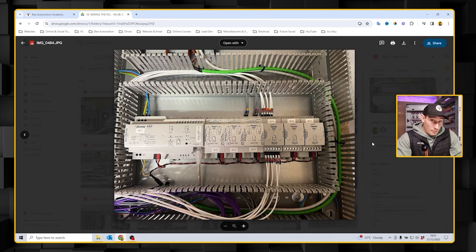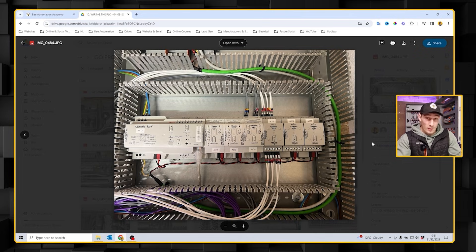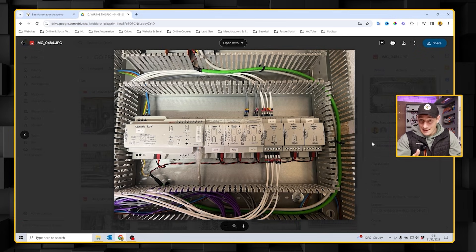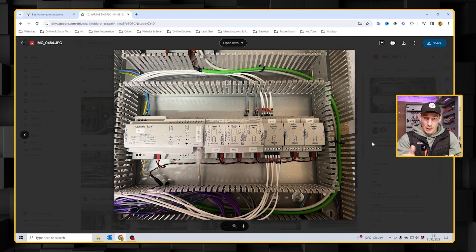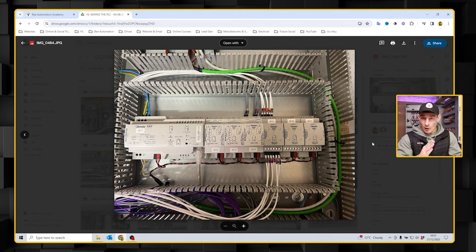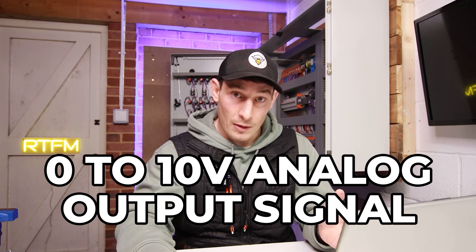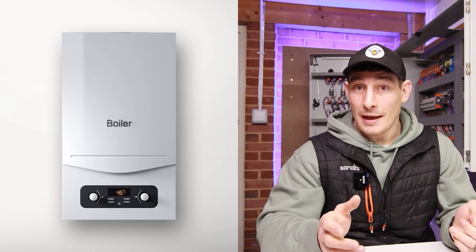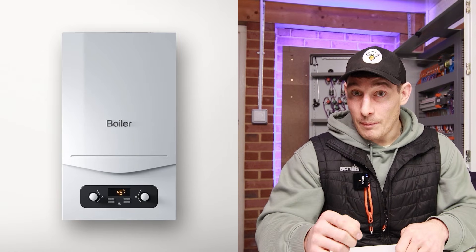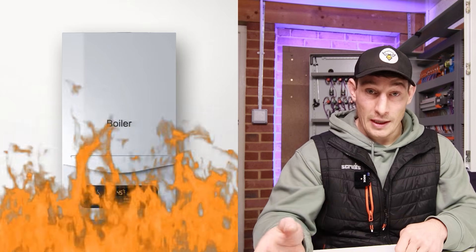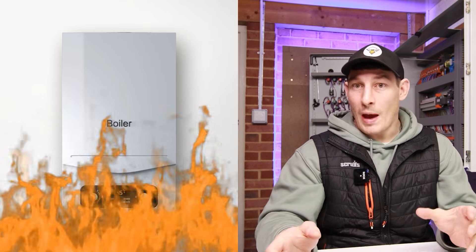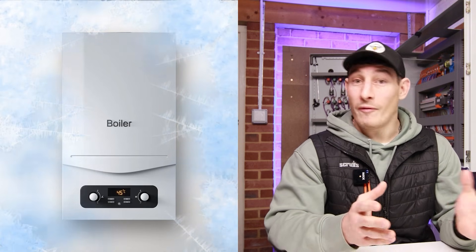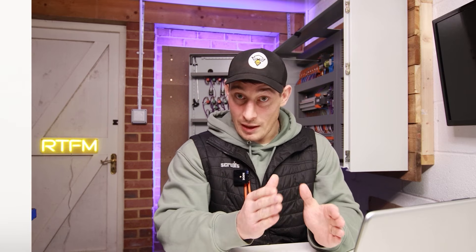Now onto the inputs and outputs. Remember what I said, these are either digital or analog. Digital they're either on or off, true or false, and then analog signals they're a range. Let's say a temperature between minus 20 degrees and plus 80 degrees with a range within that. In this project I'm using a 0 to 10 volt analog output signal feeding a boiler that's then translating that signal into heat output of the boiler.